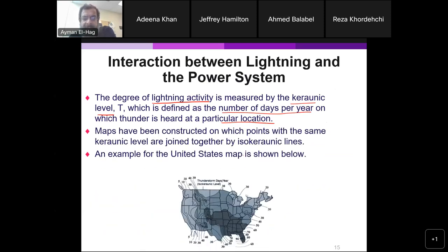Such a map looks like this, this is the map for the US. It looks like something like equipotential lines, but it's not, of course, equipotential lines. So see here, for example, to the west of the US, this is Arizona, this is 5. So along this line, this area will have 5 days in a year where you can hear thunder. But for example, here in Florida, as we know, Florida is very prone to lightning and floods, and it's 90. Okay, so such a map is very important for those who are designing the overhead system, because designing an overhead line system for a place that is subjected to a lot of lightning is different from designing a system in an area that doesn't have that much lightning.